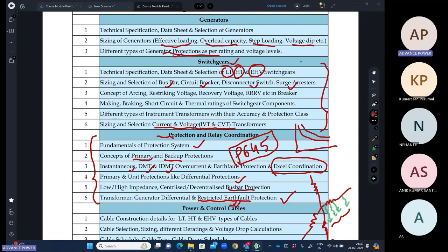and extra high voltage switchgears, because the concepts will mainly be the same for all voltage levels. The differences which will come in high voltage are some phenomena, controlled switching devices, pre-insertion resistors. Then for EHV circuit breakers you will find the SF6 type of breakers. So how it is different from ACB, VCB, all those things we'll discuss. We'll discuss different types of disconnector switches, which are center break. Then we have double break system, pantograph. One more we might have heard, the tandem isolators. These are selected based on the area requirement which you have.